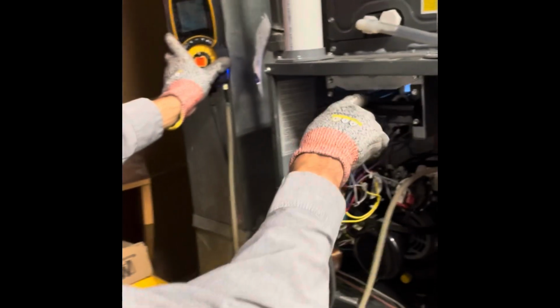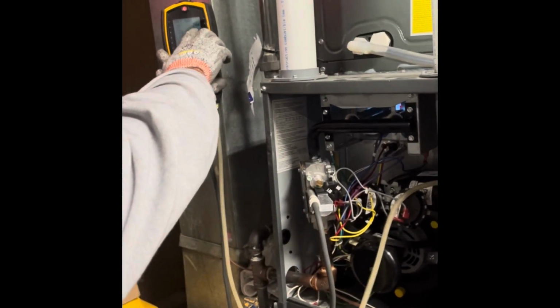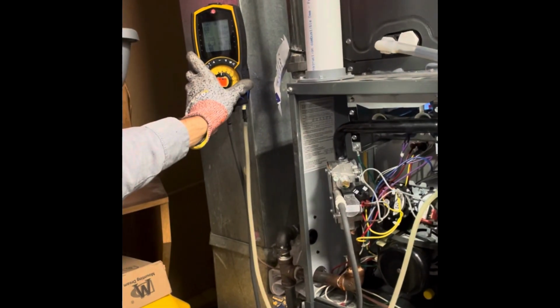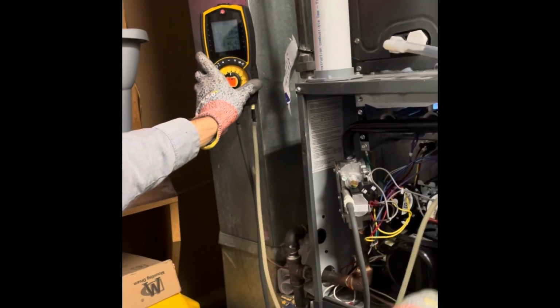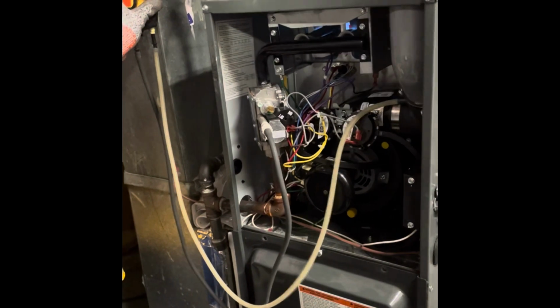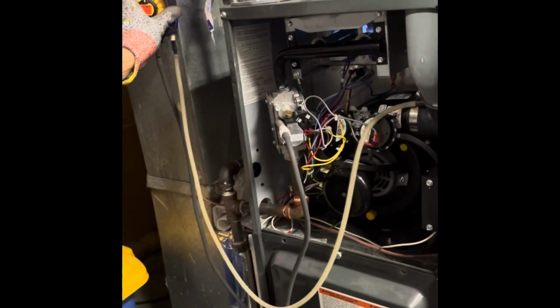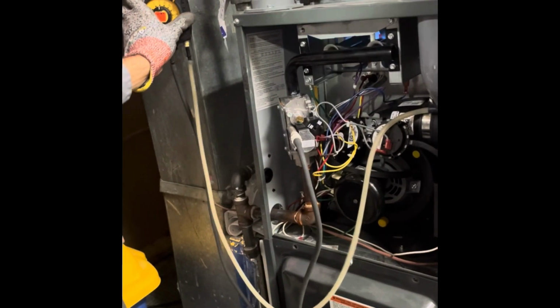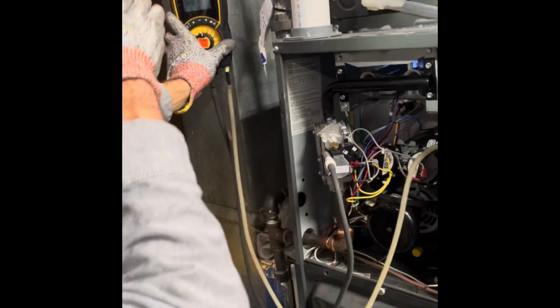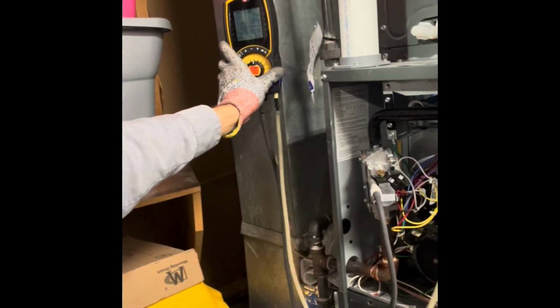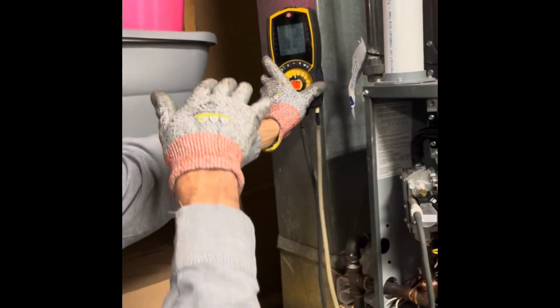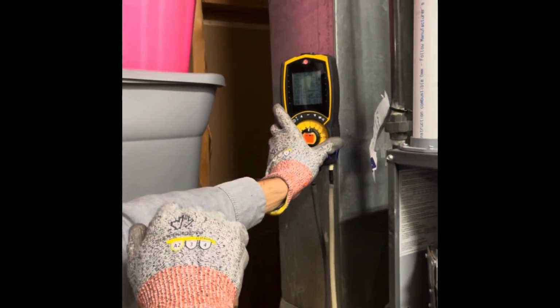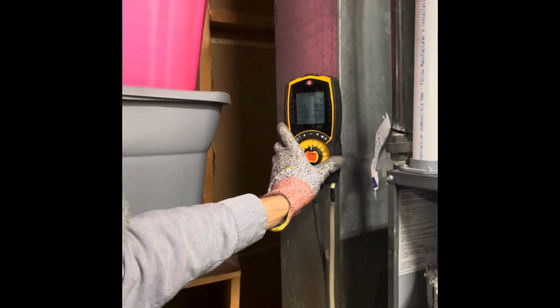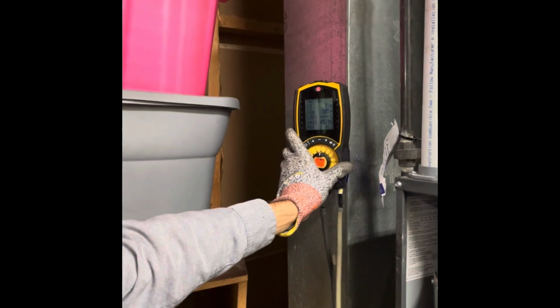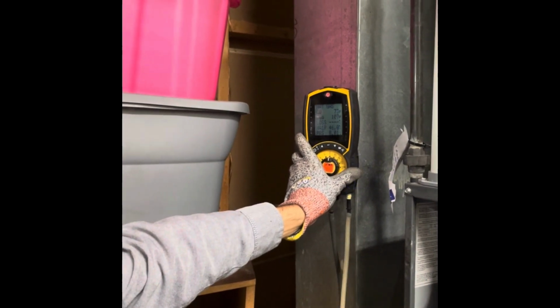If we get spiders in here, I've seen that number be at about 4,000 parts. If the condensate hoses are containing water and not allowing the water to drain, that number could be 400 parts per million. So at maintenance, we're going to keep our CO numbers as low as we can get them. It's sitting at a 71 right now, but on a maintenance, I always document my highest reading, and the highest number I saw today was 73.